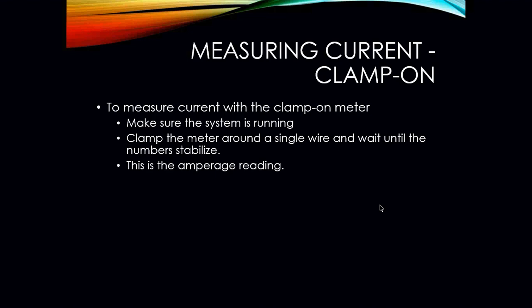To measure with a clamp-on meter, make sure that the system is on and running. Clamp the meter around a single wire and wait until the number stabilizes. When you are taking an amperage reading on any circuit, you need to do it one wire at a time. If you try to take an amperage reading over multiple wires, you are not going to get an amperage reading. The meter will actually cancel out and it will read 0. So make sure you are doing it with one wire at a time. And any reading that you take that is an amperage is measured in amps.